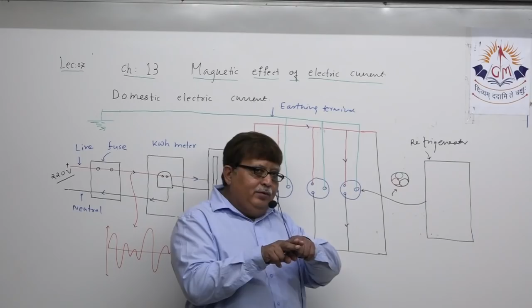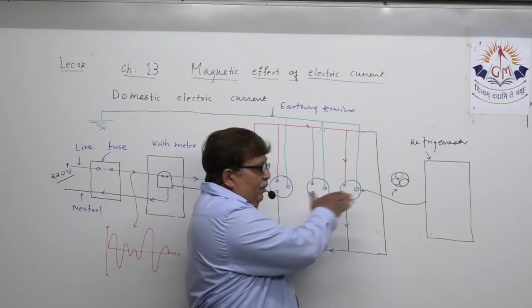Suddenly, if a hike occurs in current and by chance even the safety fuse melts, then suppose that abruptly a much larger current enters the live wire, understand, what happens? The live wire, which was actually designed for how much power rating? 15 ampere. Now if suddenly 30 ampere current starts flowing through it, it is going to overheat. Now when it gets overheated, the red insulation melts. So this wire comes in contact with green and black, because due to the overheating, insulation in earthing and neutral also melts. So 3 wires come in contact with each other, and abruptly a large amount of current enters the circuit of the refrigerator, which is called overloading or short circuit, and may damage your refrigerator.